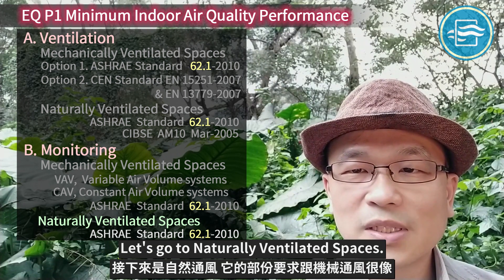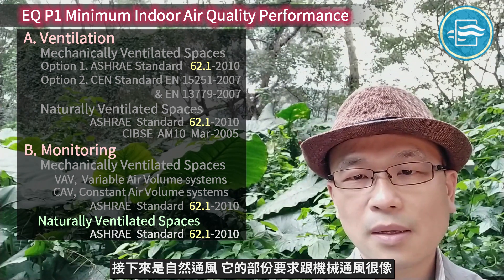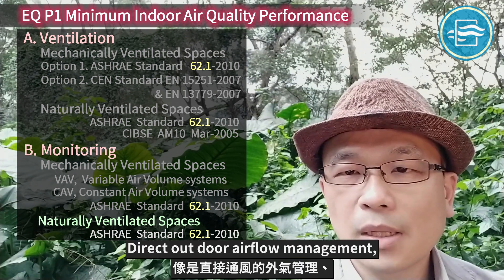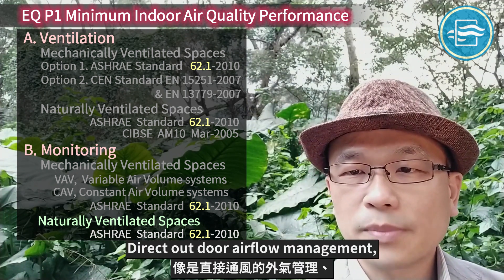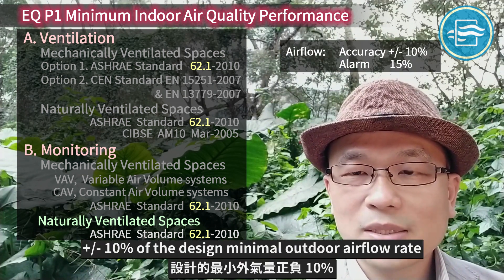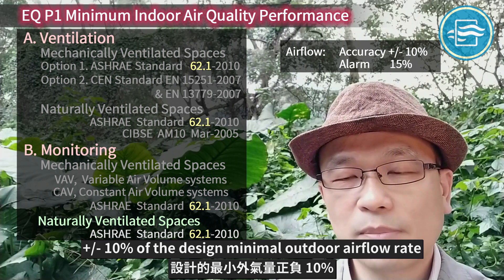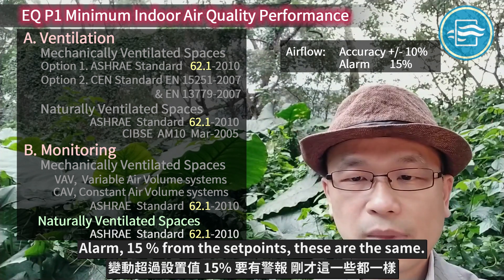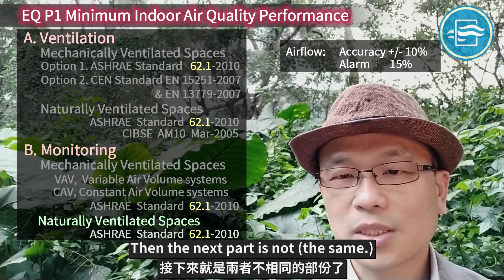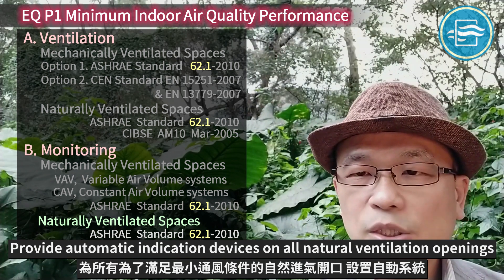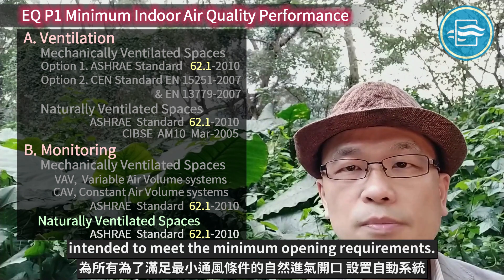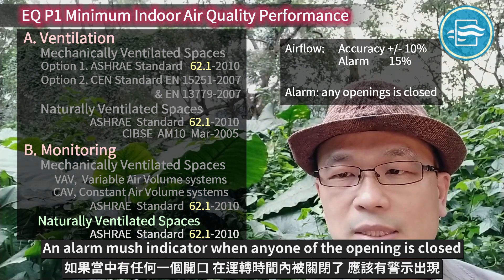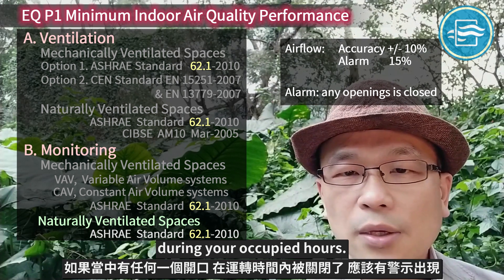For naturally ventilated spaces, some requirements are the same as for mechanical systems, such as direct outdoor air flow measurement at plus or minus 10% of the design minimum outdoor air flow rate, with an alarm at 15% from the set point. Additionally, provide automatic indication devices on all natural ventilation openings intended to meet the minimum opening requirements. An alarm must indicate when any one of the openings is closed during occupied hours.